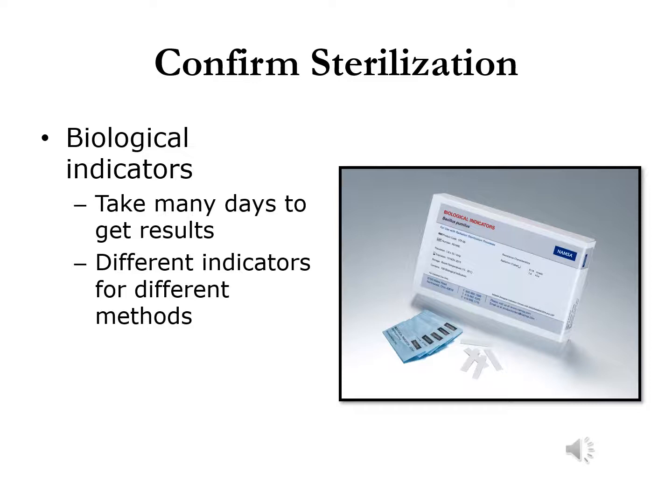Bacteria grows quicker, but it can take a long time for a biological indicator to tell us if decon has been effective. Now, there are chemical indicators also used, which just indicate that the exposure that the gas or the chemical has touched all areas. And those chemical indicators are rather quick. So the safety officer will probably use both, and she'll tell you one has come back and it's good to go, but you're still waiting on the other. Again, I just think that helps you if you have an understanding.